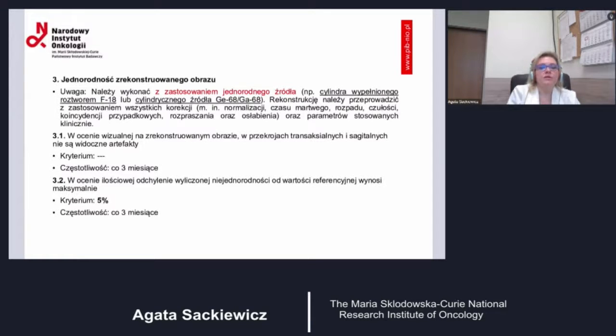Here we should use a homogeneous source. For some equipment, this can be a cylindrical source which is used for daily quality control, or it can be a cylinder filled with a solution of fluorine 18. Reconstruction should be done with all the corrections and typical parameters used in the clinical environment. In the visual assessment, we are looking at the reconstructed images. In different cross sections, no artifacts should be visible. And the frequency is every 3 months.